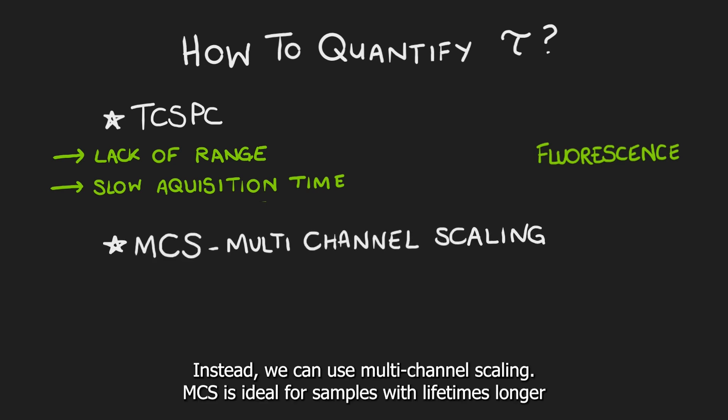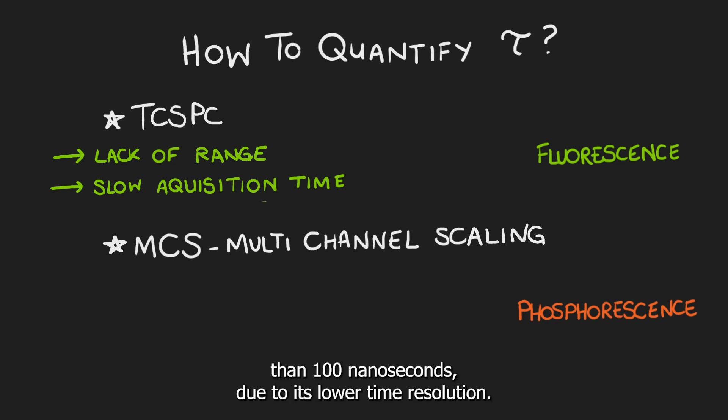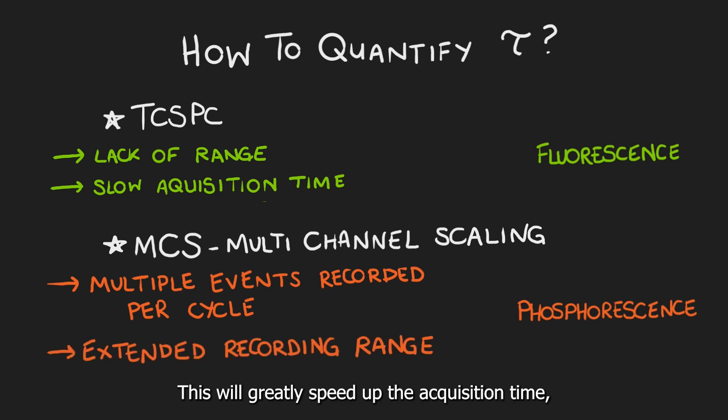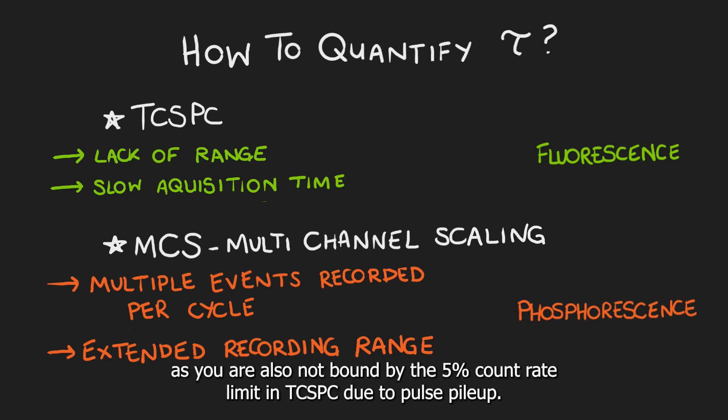Instead, we can use multi-channel scaling (MCS). MCS is ideal for samples with lifetimes longer than 100 nanoseconds due to its lower time resolution. In MCS, we will collect multiple photons per pulse, unlike TCSPC. This will greatly speed up the acquisition time, as you are also not bound by the 5% count limit in TCSPC due to pulse pileup.